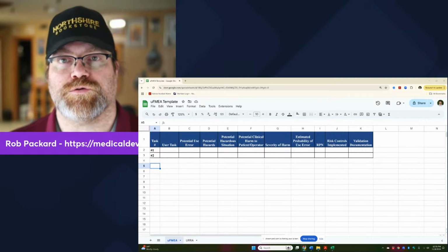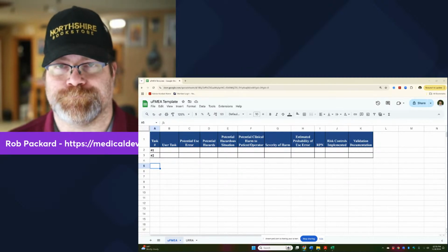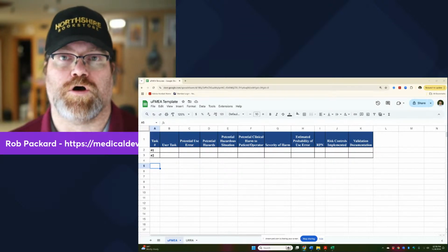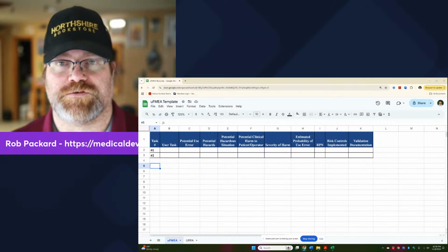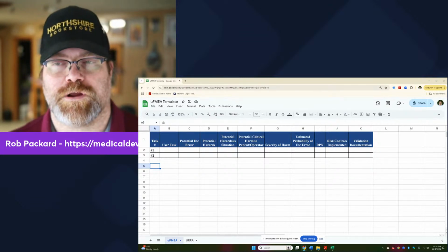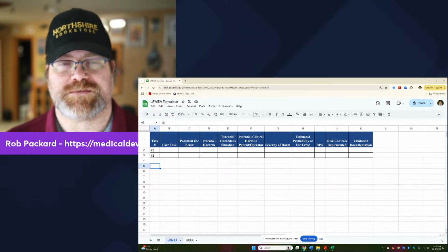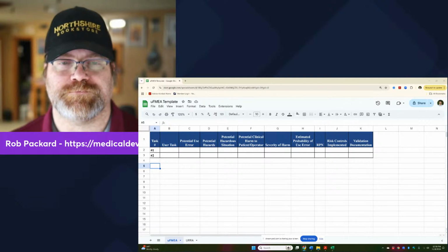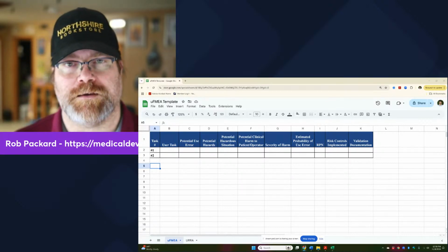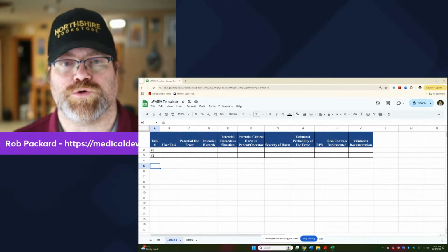The risk controls will be prioritized based on severity typically, or that RPN number. So I tend to focus on the severity, the things that are most likely to cause death or serious injury. Let's fix those first, prevent those, and then we'll worry about the lower severity items and worry about the probability later. Once we've addressed the highest risk items, now let's worry about things that happen frequently. And then the last column is the validation documentation, so making sure the risk controls work.